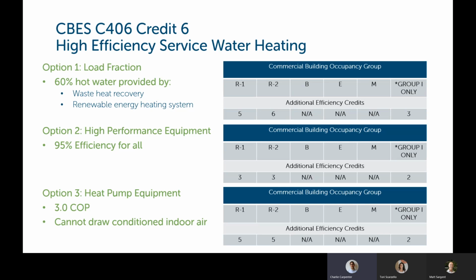The third option is heat pump water heating equipment, where you would need to have an increased coefficient of performance of 3 for the equipment. And you cannot draw conditioned building air into those heat pumps unless it is air that was otherwise going to be exhausted from the building to the outside. That's the only time you can use conditioned air within the building. And I think our little icon's in the way at the bottom, but you would get 5 points for R1, 5 points for R2, and 2 points for an industrial group there.